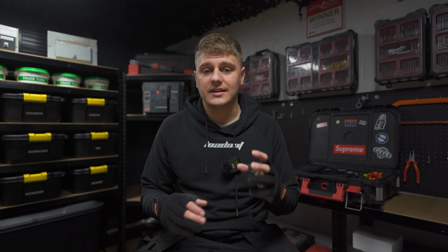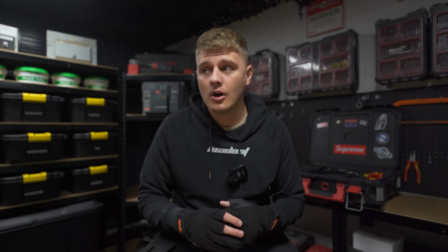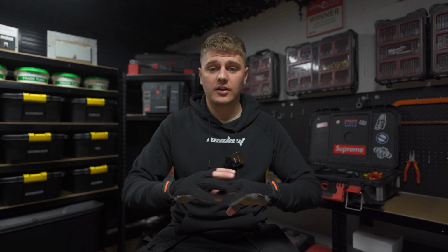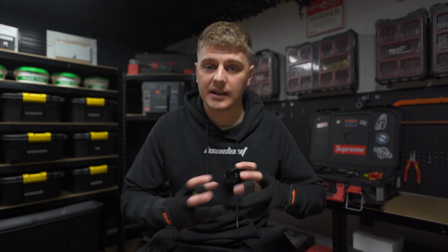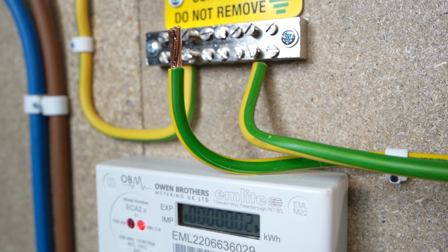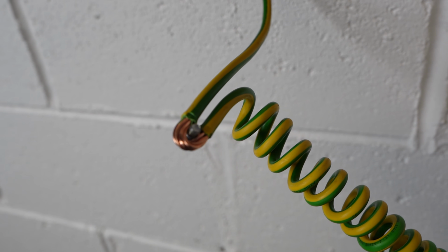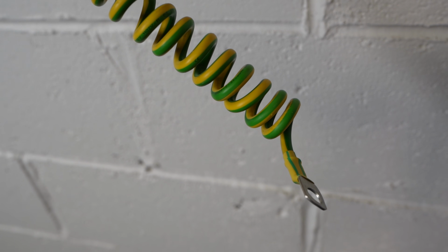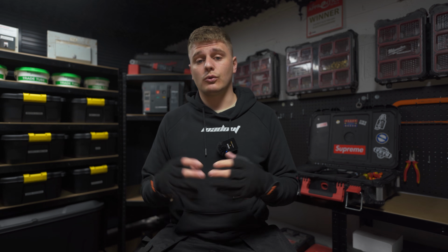So while it's good to use the test method set out earlier in the video, on complex installations with multiple bonds and a vast array of extraneous or exposed conductive parts that are all interconnected, it may be more worthwhile to isolate the individual bonding conductors and test them independently before carrying on with the rest of the test, to confirm a sound connection to the metallic part and that sort of stuff. This is also a common fault under exam conditions, so any apprentices or learners, just watch out for that one.